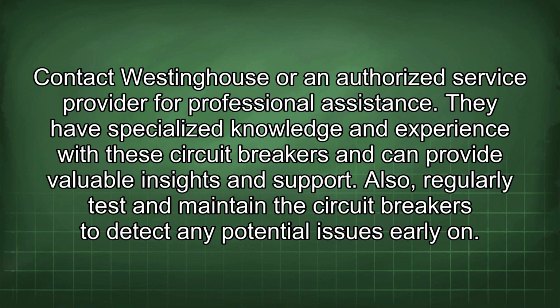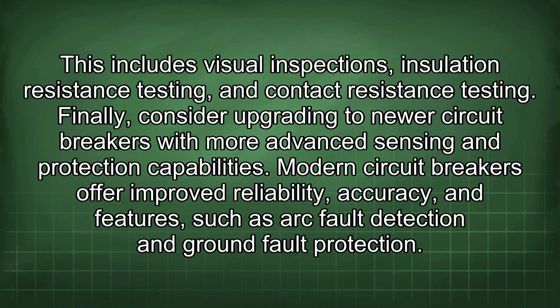Also, regularly test and maintain the circuit breakers to detect any potential issues early on. This includes visual inspections, insulation resistance testing, and contact resistance testing. Finally, consider upgrading to newer circuit breakers with more advanced sensing and protection capabilities. Modern circuit breakers offer improved reliability, accuracy, and features such as arc fault detection and ground fault protection.